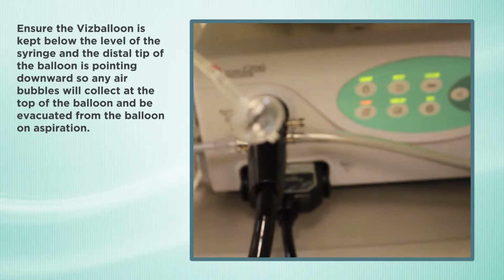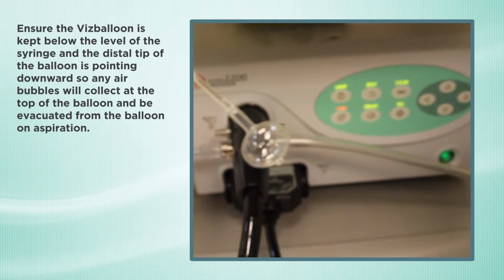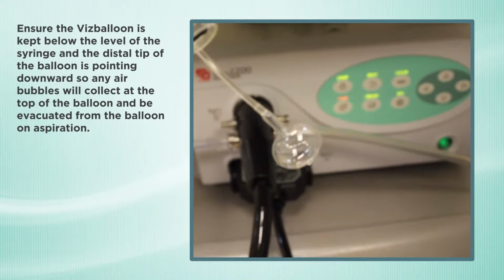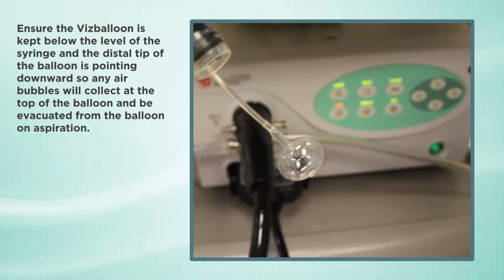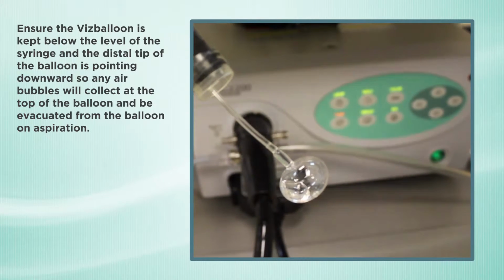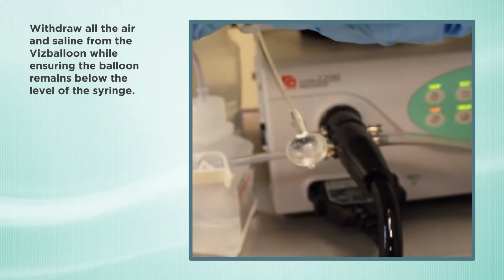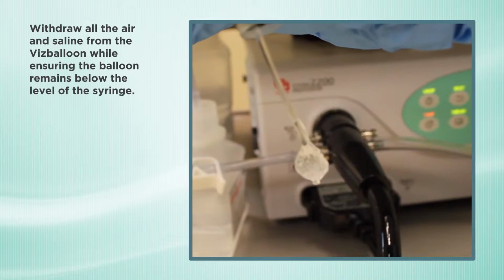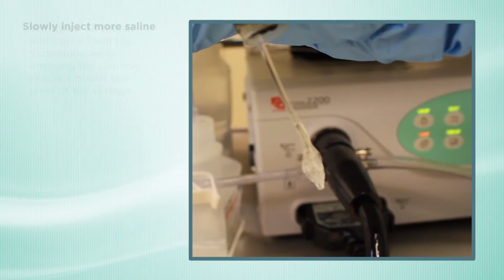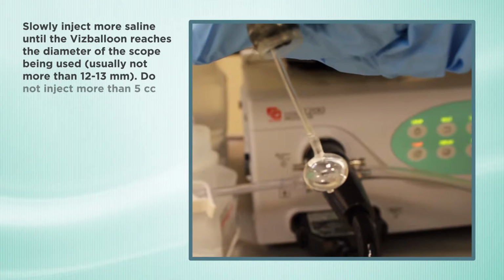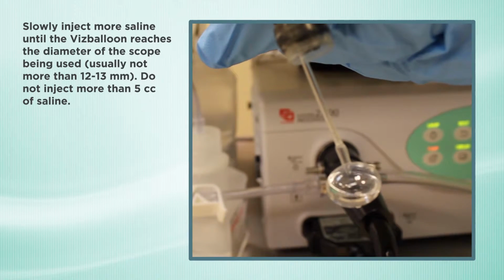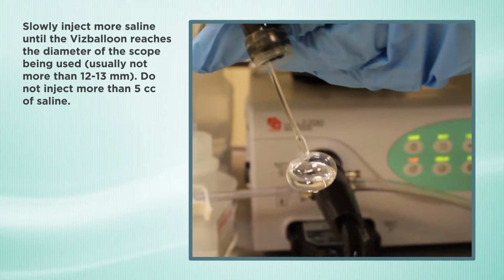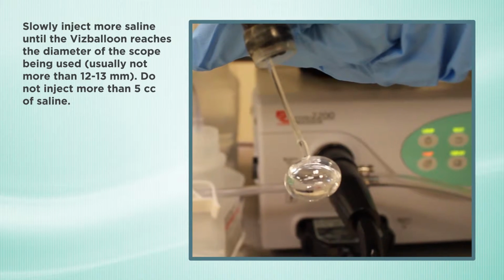Ensure the Vizballoon is kept below the level of the syringe and the distal tip of the balloon is pointing downward, so any air bubbles will collect at the top of the balloon and be evacuated from the balloon on aspiration. Withdraw all the air and saline from the Vizballoon while ensuring the balloon remains below the level of the syringe. Slowly inject more saline until the Vizballoon reaches the diameter of the scope being used, usually not more than 12 to 13 mm. Do not inject more than 5 cc of saline.